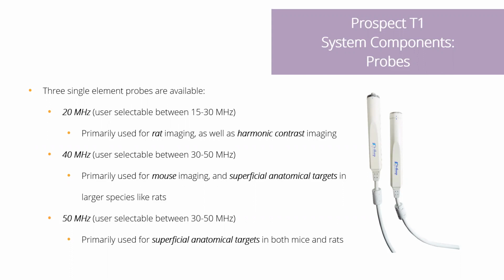And when we're talking about ultrasound, we think about frequency as it relates to depth of penetration. And so as we go down in frequency towards the 20 megahertz probe, we increase the penetration, and that's where we would typically use these probes on rats. The 40 megahertz would get all the way through a mouse. But if you were looking at a superficial anatomical target on a rat, such as, for example, the carotid artery, you could use either the 40 or 50 megahertz probe to provide you with higher resolution images. So it really just does come down to a conversation about the research that you want to do, the animal models, as well as your anatomical targets to understand which probe would suit you best.